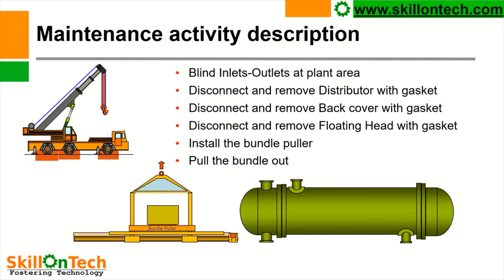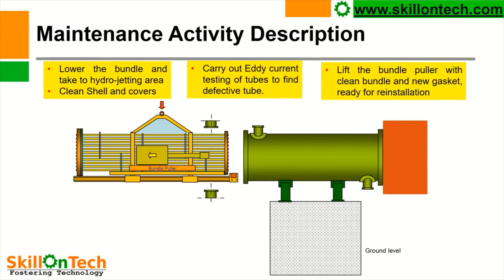After complete draining of the heat exchanger and after issue of safety work permit: disconnect the channel cover, remove the gaskets, disconnect the shell cover, remove the gaskets, disconnect the floating head with gasket, and install the bundle puller. Pull the bundle out, lower the tube bundle and take it for hydrojetting. Clean shell and covers. We shall also ensure if there are any liners provided in the shell cover, in the shell, in the back cover — then all those liners shall be checked for any damage. Eddy current testing is also essential.